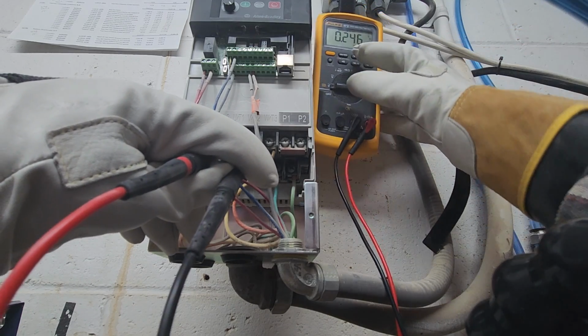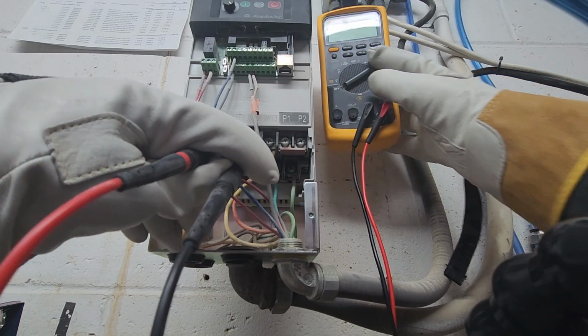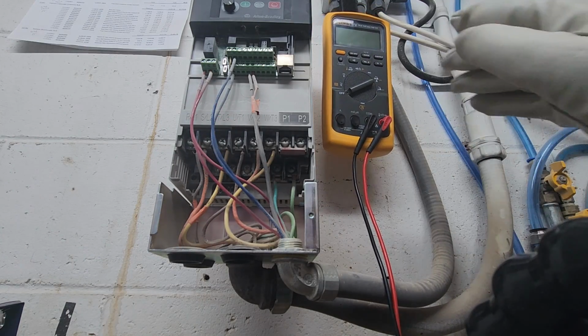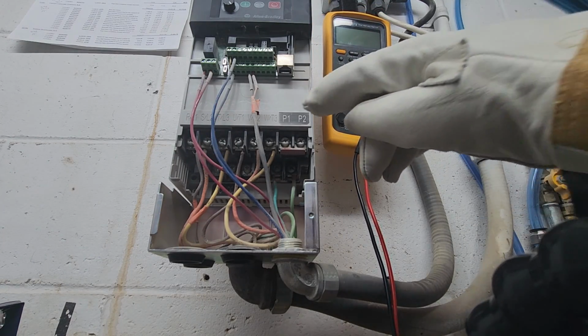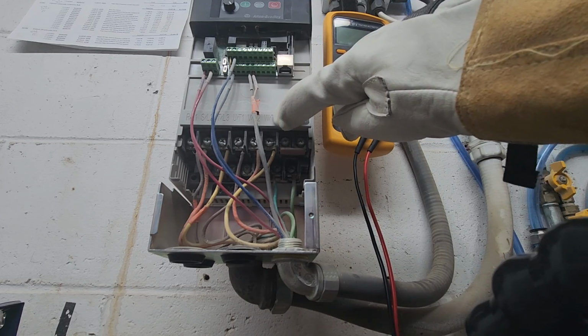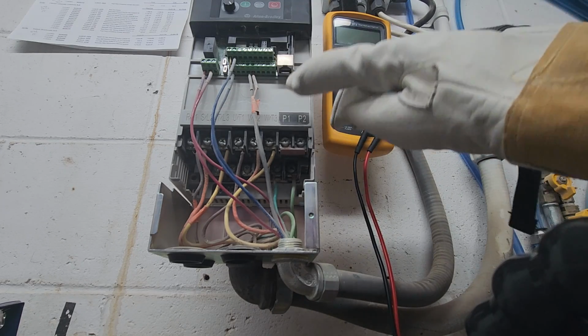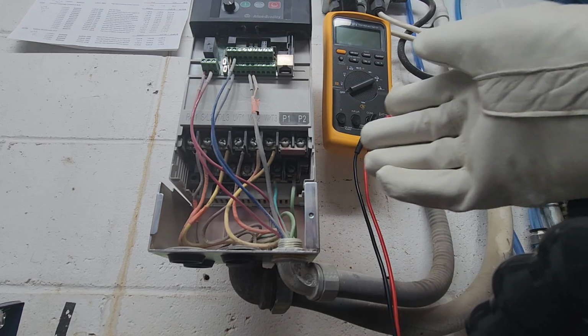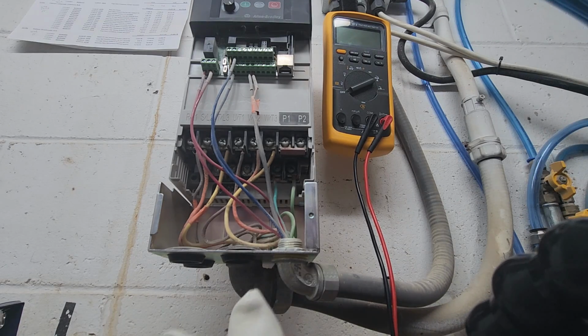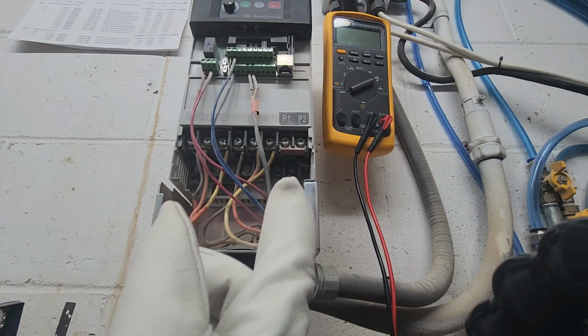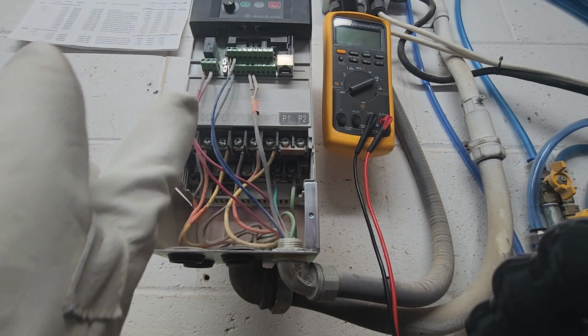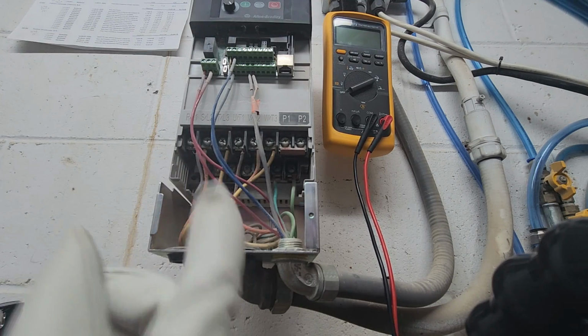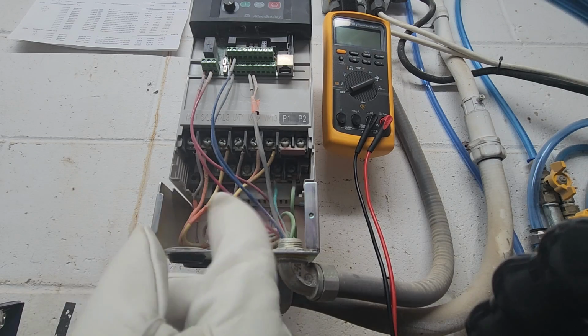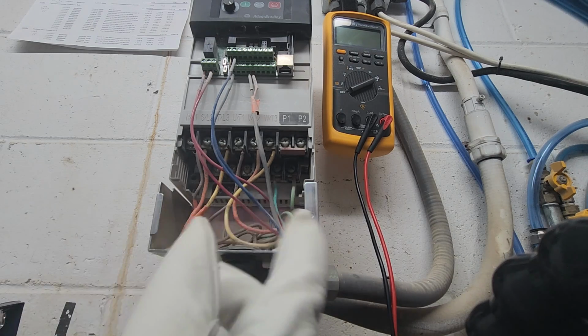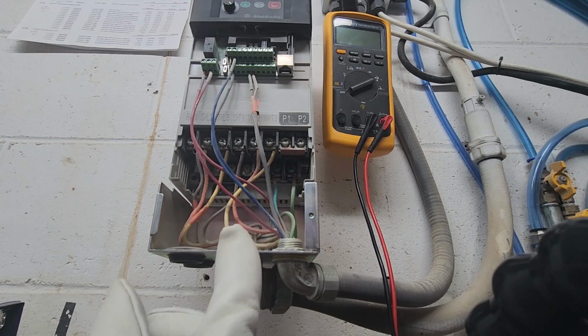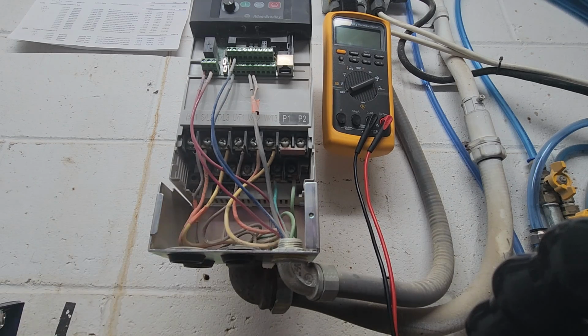Yeah, see, we've got our VFD off and our whole PLC system shut down for the weekend, so we're not going to get a reading. But if you measure your peak voltage on your terminal 1 to terminal 2 or 2 to 3 or 1 to 3, you should be getting as your peak voltage 680 volts. Even if your VFD says it's only outputting 240 volts at 30 hertz, you're still going to be getting the reflections and harmonics back from your rectifier. So you will be able to read 680 volts on your output side.